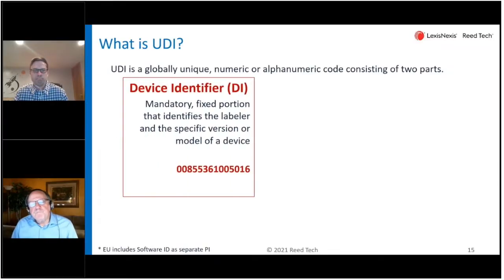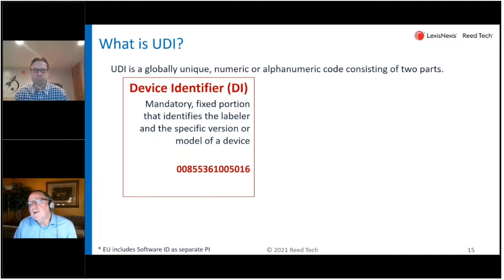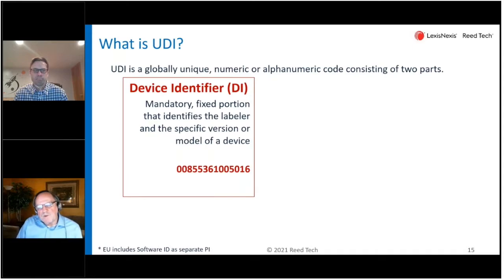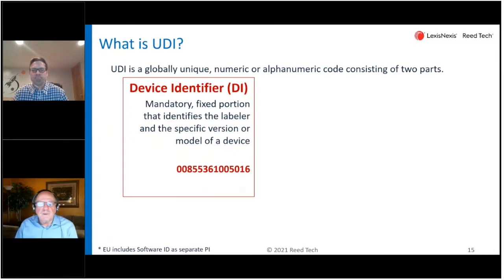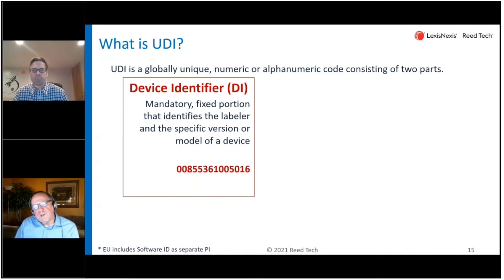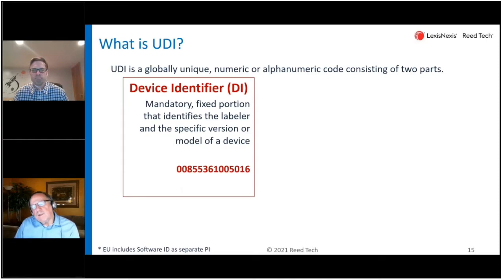UDI is a globally unique alphanumeric or fully numeric number consisting of two parts. The first part is the device identifier portion, which is required. It includes identification pointing to a labeler — so a manufacturer would have a unique identifier — and also embedded in that number is identification to a particular product version. Each new version or model would have a unique number, and embedded in there is also a package indication and a check digit.